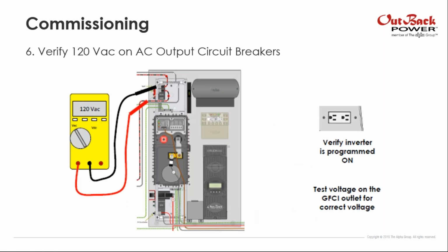Then check that you have 120 volts in the AC output circuit breakers. You will check it in the terminals that are connected to the inverter, so it will be from the AC output breaker and the bus bar of neutral. If you do not have 120 volts here, be sure that your inverter is on. By factory, it could be on, but if not, you will check the jumper inside the inverter in order to check that it is on.